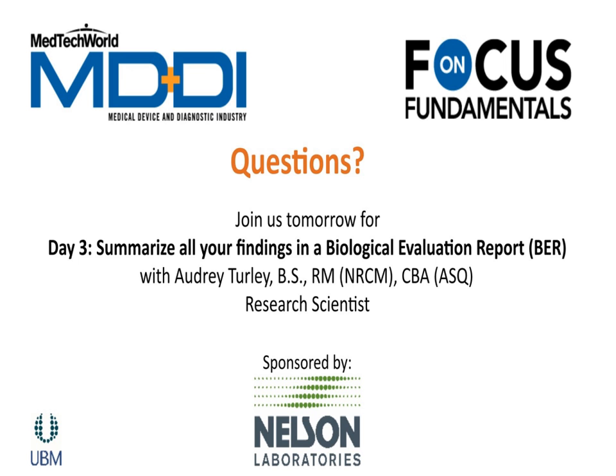Thank you. The next one is, some companies use 58 kg weight of an adult female instead of 70 kg for an adult male in the calculations. Is this necessary? So what we do here is, if the device is going to be used solely on males, we will just use the 70 kilograms. This is commonly applied in the pharmaceutical industry as well.